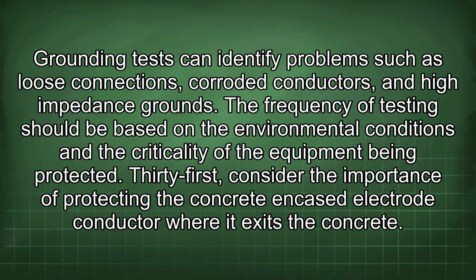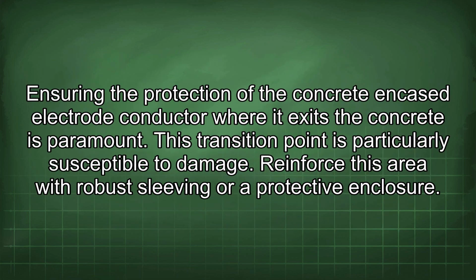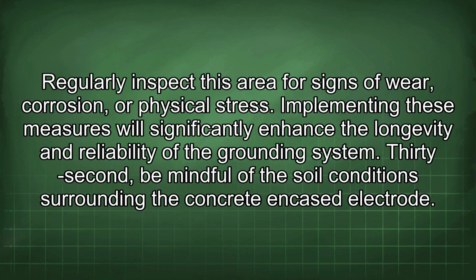31st, consider the importance of protecting the concrete encased electrode conductor where it exits the concrete. Ensuring the protection of the concrete encased electrode conductor where it exits the concrete is paramount. This transition point is particularly susceptible to damage. Reinforce this area with robust sleeving or a protective enclosure. Regularly inspect this area for signs of wear, corrosion, or physical stress. Implementing these measures will significantly enhance the longevity and reliability of the grounding system.